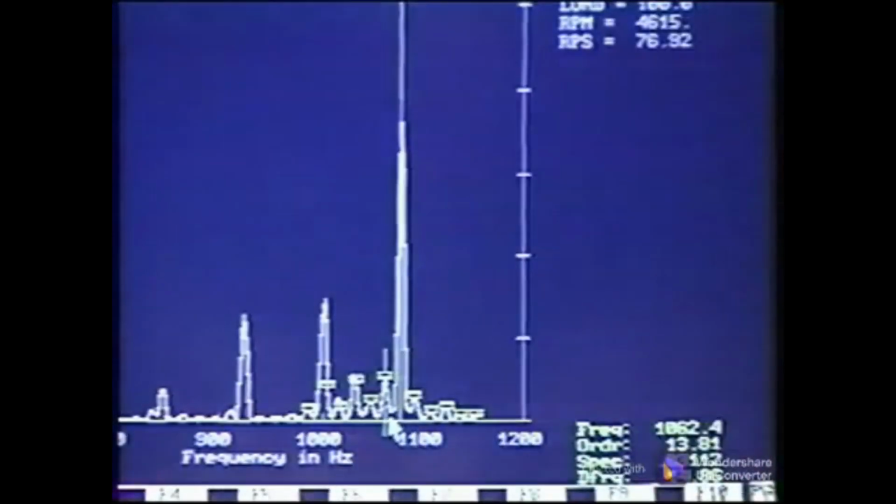It is important to note that these sidebands may not be discernible if the resolution is not high enough, especially in the case of multiple frequency sidebands. A second, third, or multiple harmonic of the sideband for one gear may be near the one-time sideband of the other gear, and poor resolution will cause them to appear as one peak.